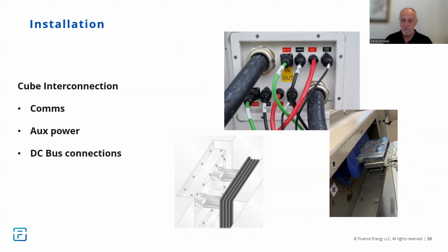The interconnection panel, which I mentioned earlier, just connects the comms, the LV power system, which is a single phase, and then the DC bus connectors, which are at the top of the cubes. And you can see from the photographs at the bottom the flexible nature of these bus connections to allow for minor differences in distances between the cubes.